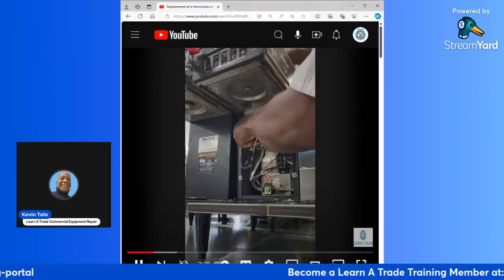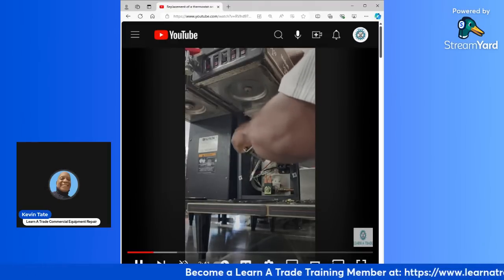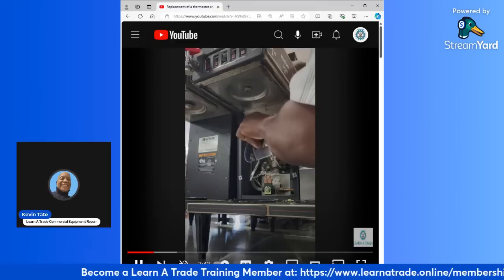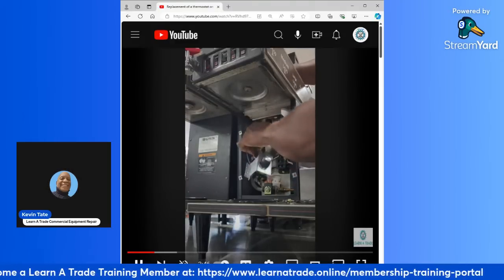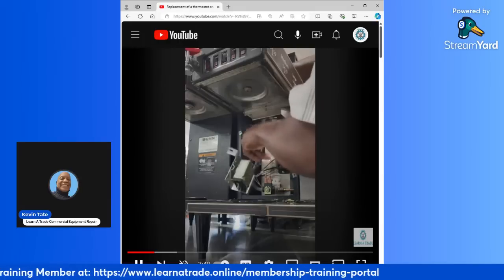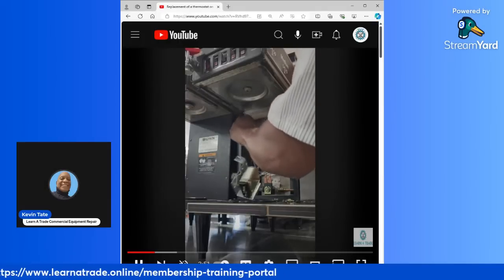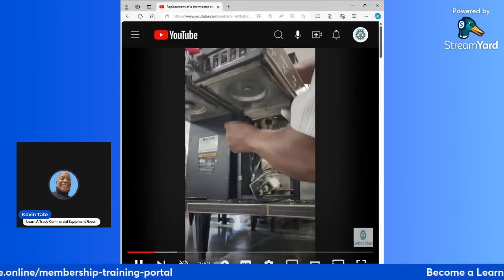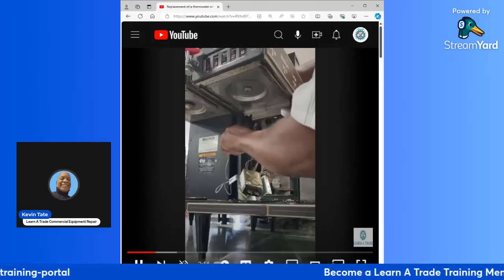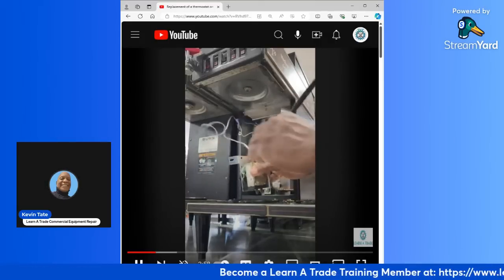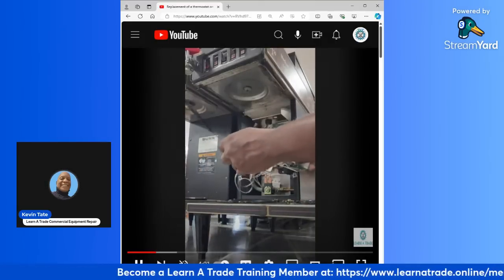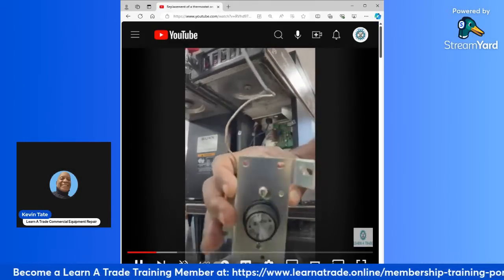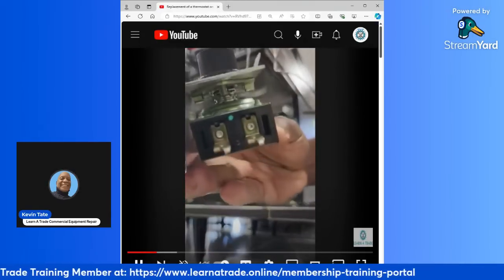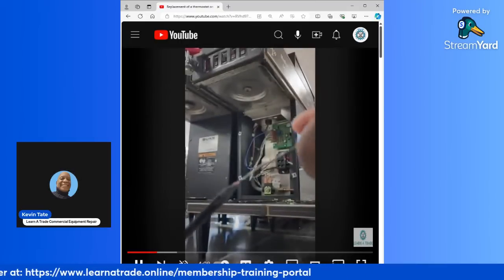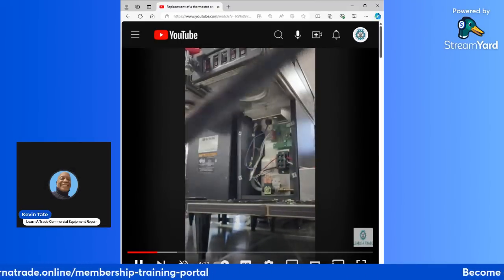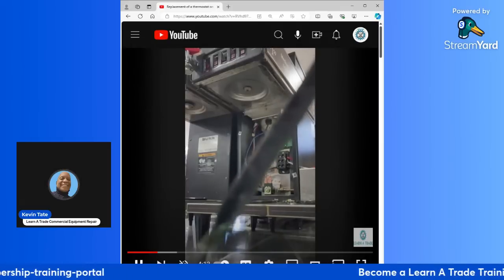Okay, now I have the blue and the black wire disconnected, and right now I'm just feeding that thermostat probe, the bulb, through the top of the machine to remove the whole assembly. And that's the whole thermostat assembly right there. That's a better look at it. And those are the terminals down there. There's the bulb end of the thermostat assembly.